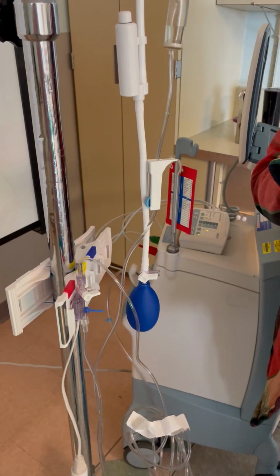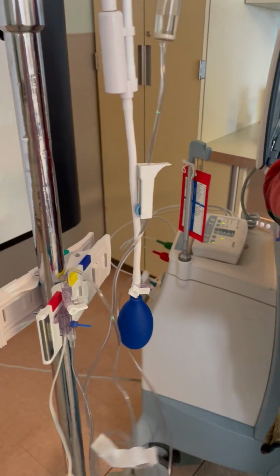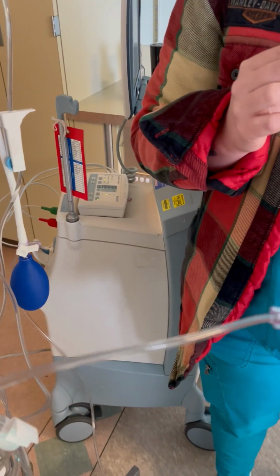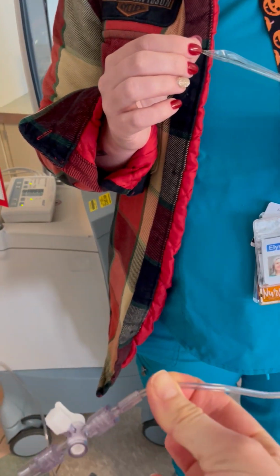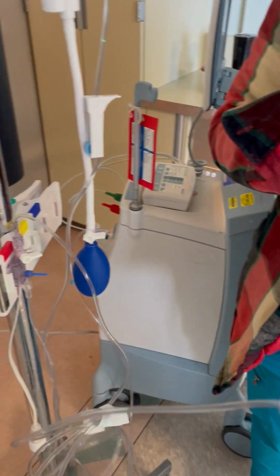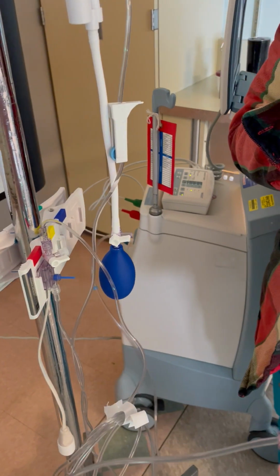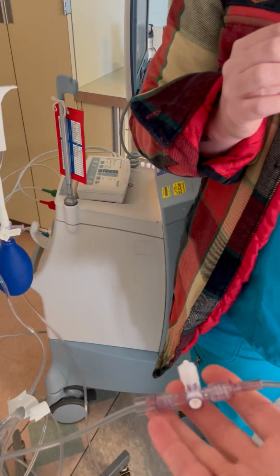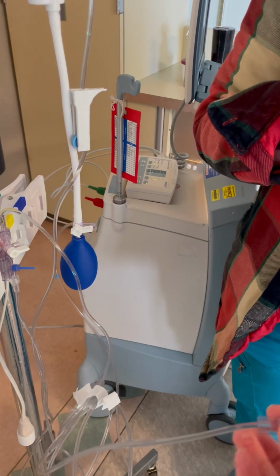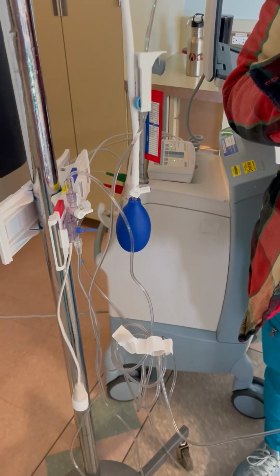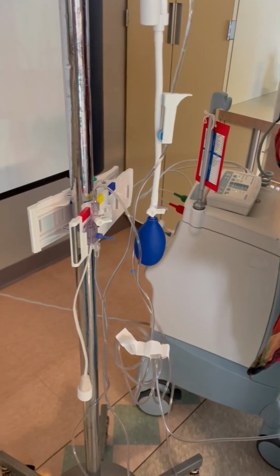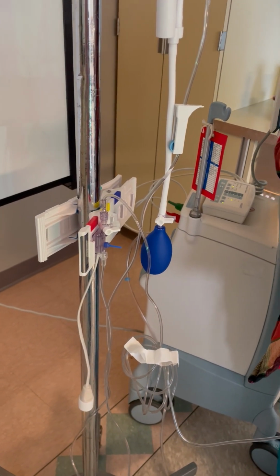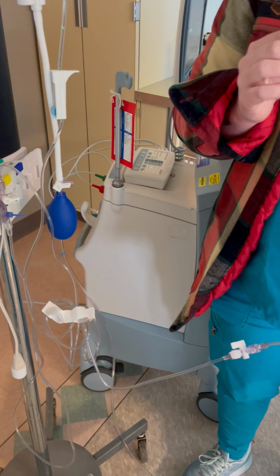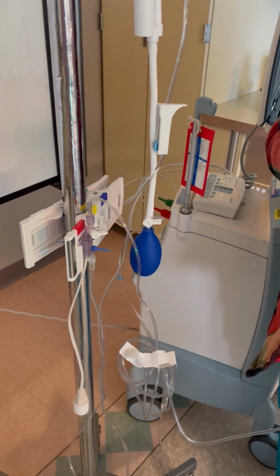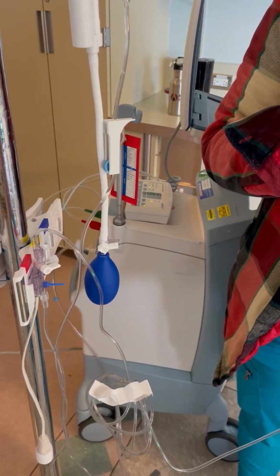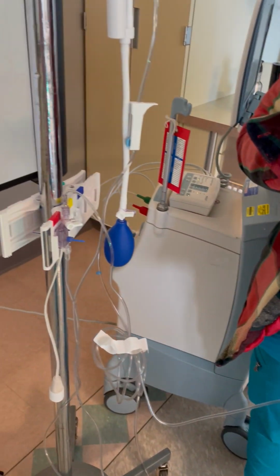If all of that checks out, then you will want to try, first of all, an aspirate. So you can aspirate from here and see if you can get a little bit of blood back from the catheter. If you're not getting any blood back, then chances are you will not be able to flush the system and there might be a clot or something sitting on the end. So we would want to notify the physician, and then from there we have a couple of options. We can either change out the balloon catheter, or you can take a radial art line pressure or an art line pressure from somewhere else on your patient's body, and you can send that information into the back of the console, and you can allow the balloon to pump based off of that waveform.